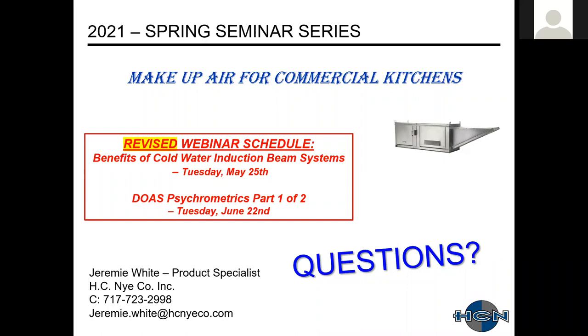You're going to require more makeup air. Island hoods are not the best option, but there are certain situations where you have to use an island hood where there's no way around it, and then you just have to design with that in mind. So utilizing transfer air for those types of systems is usually a good bet. And if you're going to go with a dedicated makeup air unit, use a perforated supply plenum all the way around the hood, and still utilize that transfer air. So let's say you're going to use 50-60% dedicated, and then the rest from the transfer air from the space. Usually with island hoods, you see them in larger facilities, casinos, some hospitals and stuff like that. So usually it's a bigger system that has the capacity for that transfer air.